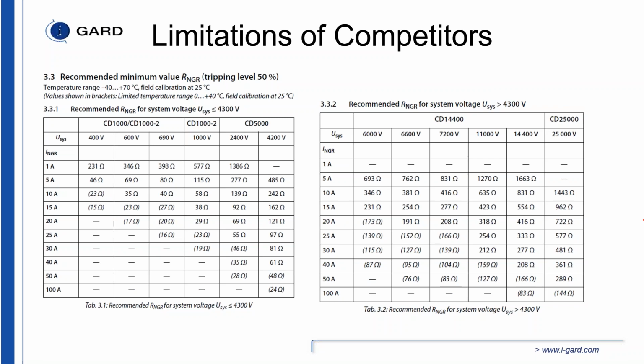Voltages, we can normalize the voltage using our sensing resistor from 480 volts all the way up to, well, we've gone as high as 36 kV, and I believe we're working on a 72 kV model right now. So the difference is how we comply: we put a potential on the system that has a higher frequency, and for really, really low resistance values, we change the frequency in order to observe the change in resistance.